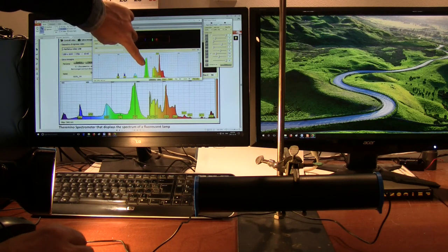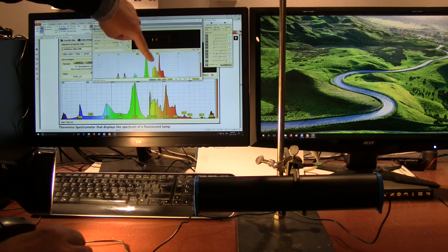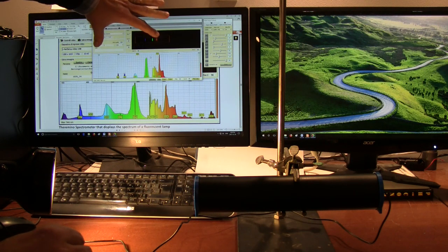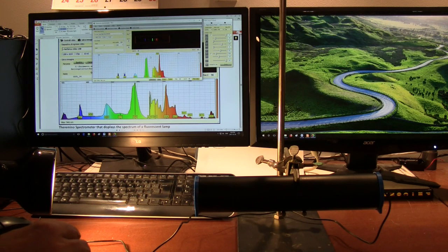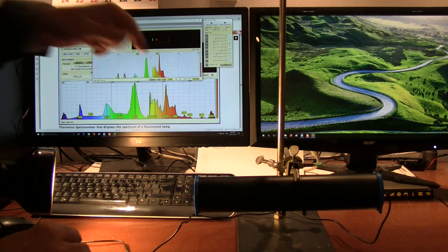You see this one's already at about 546, 545, but we can also adjust the upper 600 to bring this one into scale. And you can see once we've made our adjustments, then our spectrums match, and we're getting fairly good resolution on the line, similar to their calibration graph.